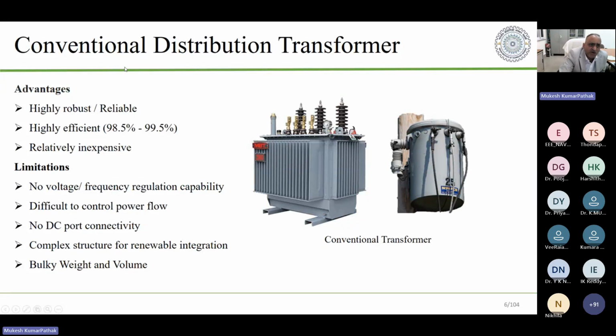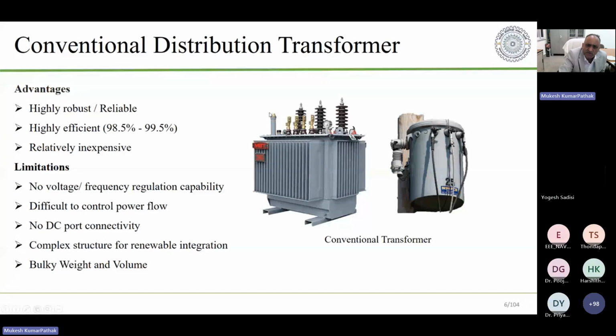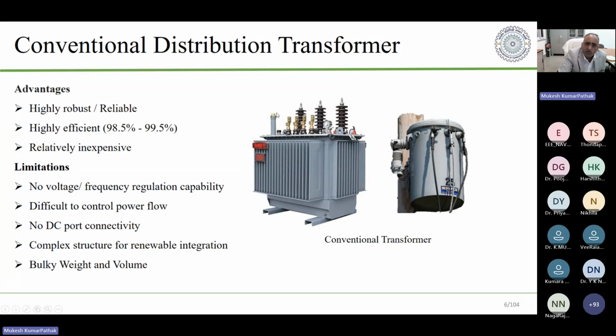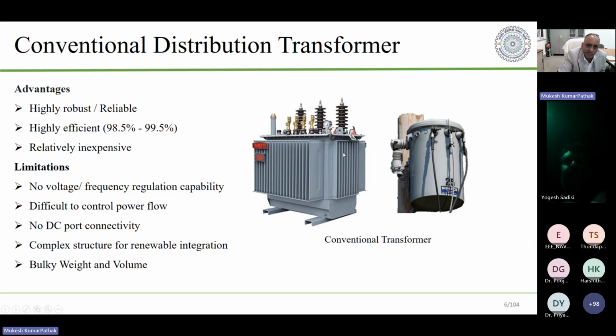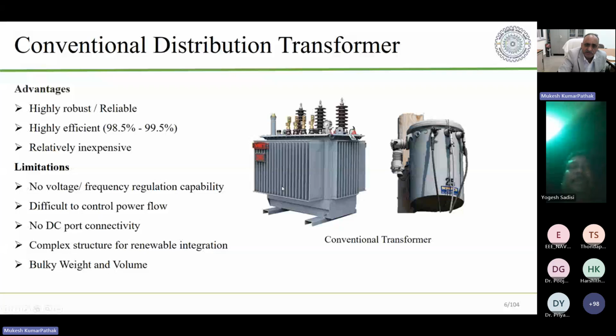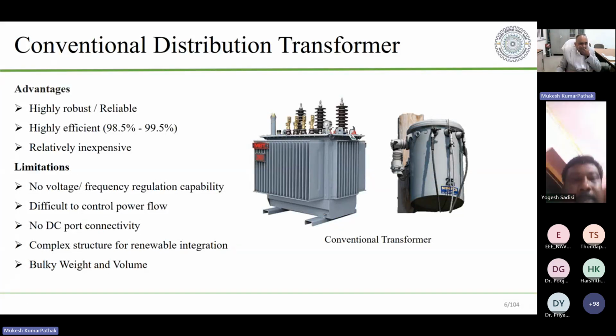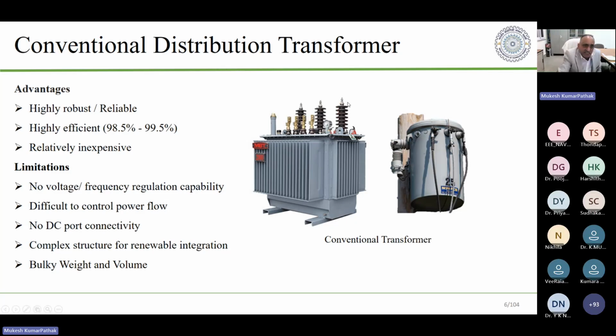The distribution transformer as such is a highly robust and reliable system. We know that the transformer's failure rate is very low, and we almost always get electricity from these transformers even if we overload them. So they have a lot of overloading capability, and they have very high efficiency. Efficiency of these transformers is sometimes more than 99%.